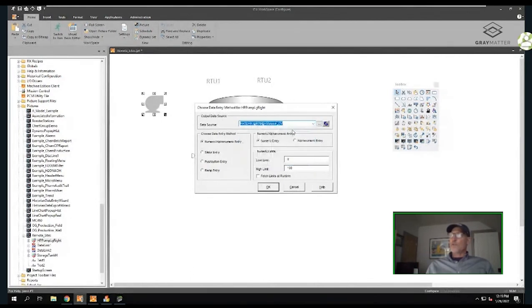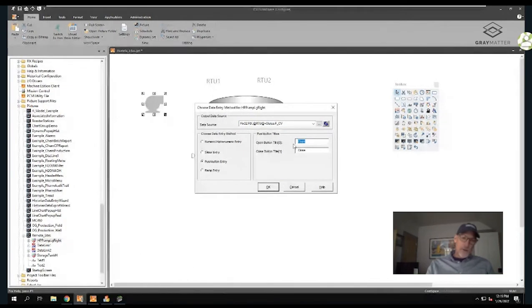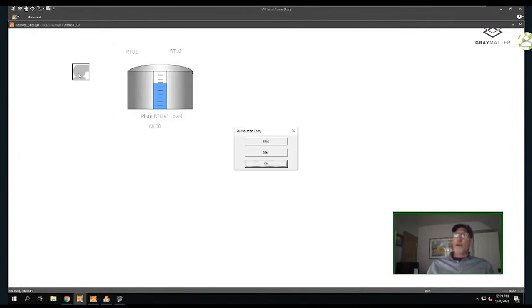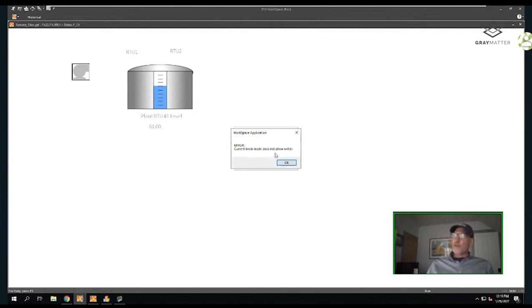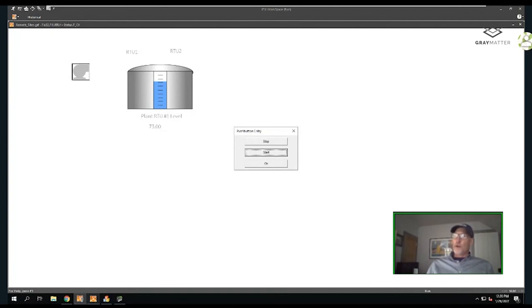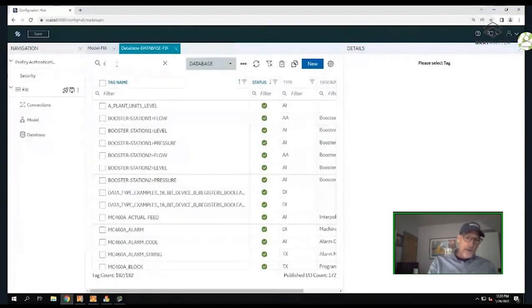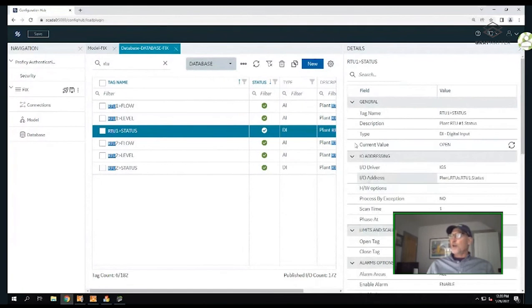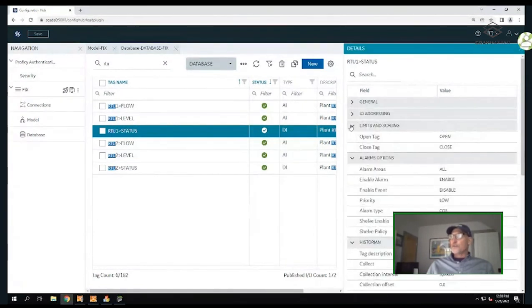I want to control the current value of that tag, put a push button on so it can go to zero state (stop) or one state (start). I'll save that. As I go into RTU1 and try to make a change, I get an error: Current block mode doesn't allow writes. I need to make a tag update, and I'll do that in Configuration Hub. I'll select my status tag - these are the same iFIX fields you're used to - and to write a value, you need to enable output.